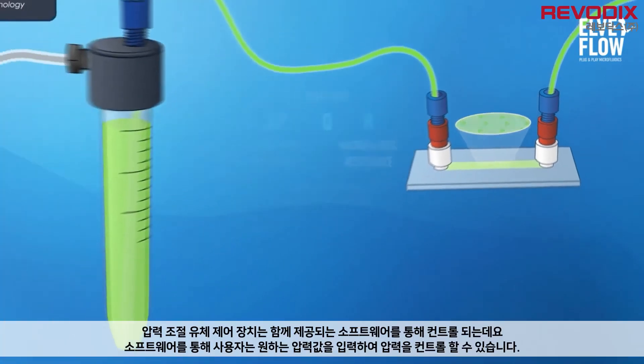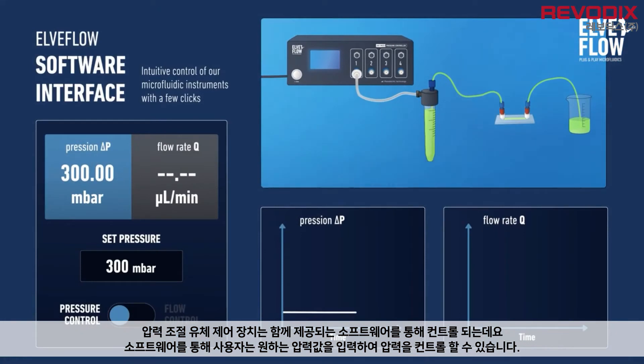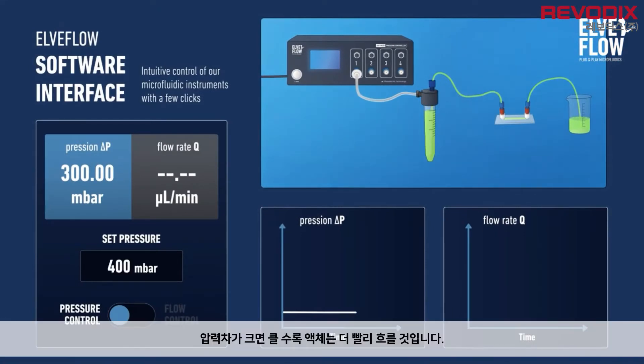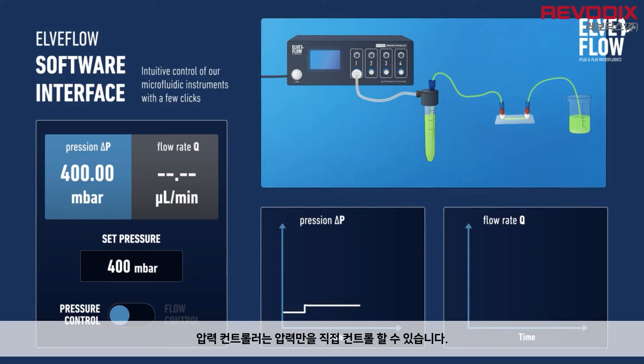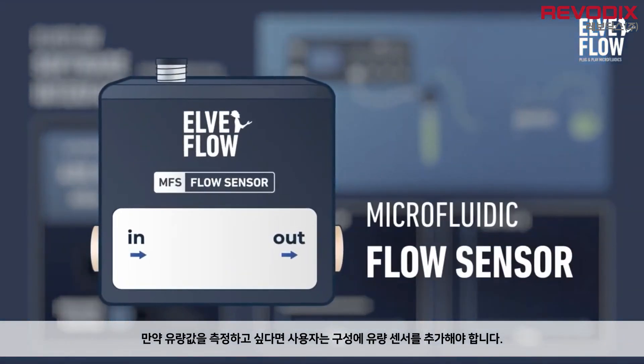The pressure-driven flow controller is controlled with software, which allows you to control the pressure by setting a target pressure. The higher the pressure difference, the faster the flow rate gets. A pressure-driven flow controller only provides direct access to pressure. To access flow rate values, one needs to add a flow rate sensor to the setup.